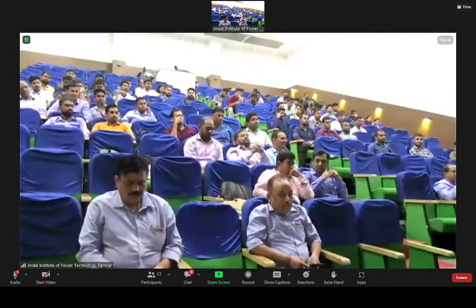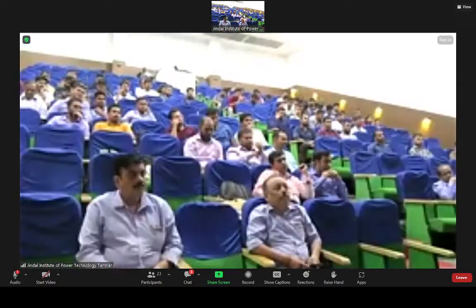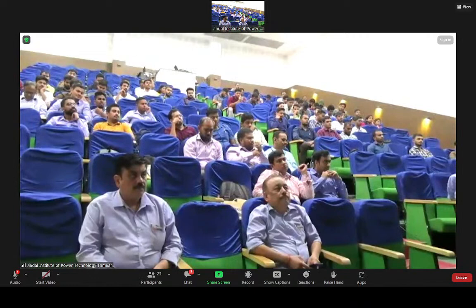Actually, these are all from the prime mover background. For steam turbines, there is typically a recommended range. See, for steam turbines, it is usually recommended in the range of 2.5 to 8%. If you have experience with a KWU turbine, for example a 210 or 250 megawatt, there you have the hydraulic governor. Do you know the droop setting in that hydraulic governor? It is 7%, whereas in the electro-hydraulic governor, it is 5%.